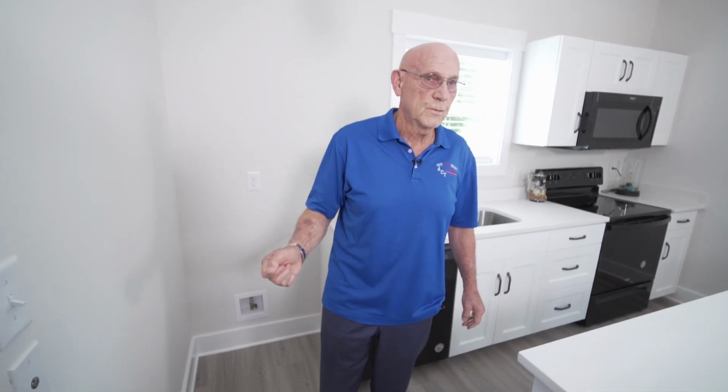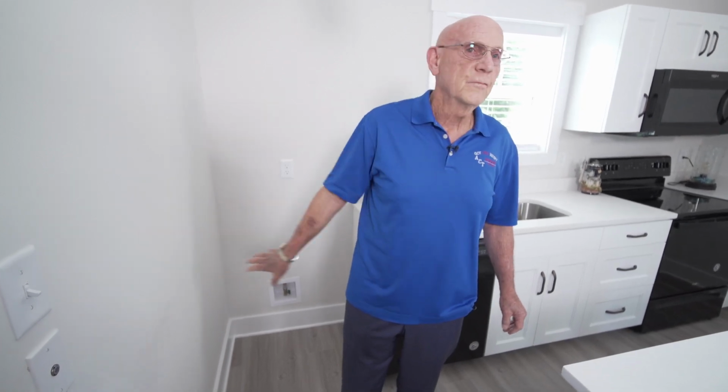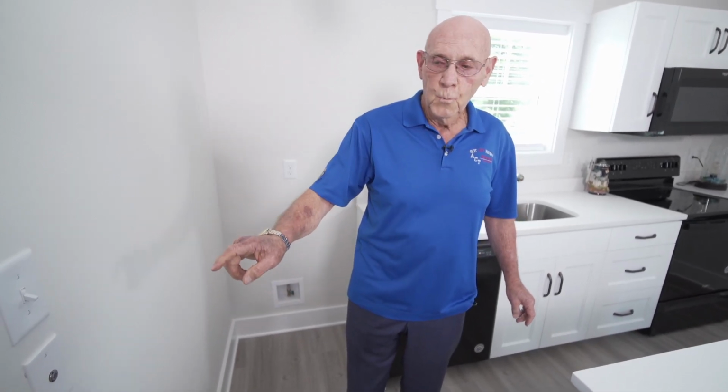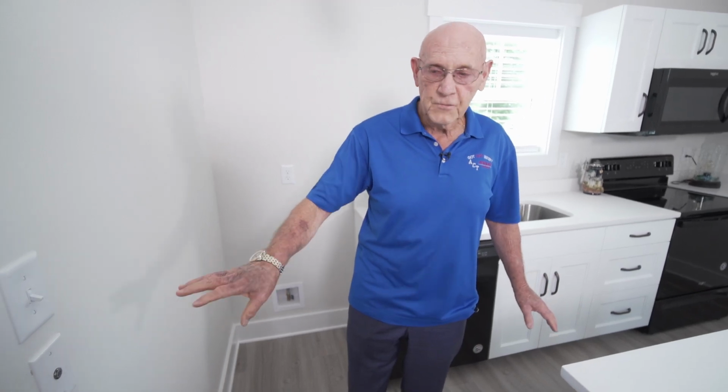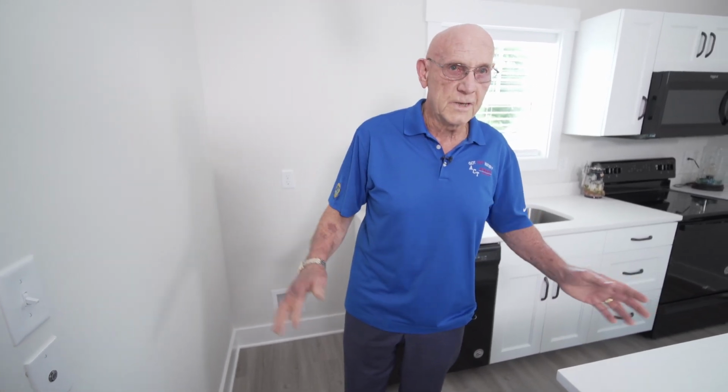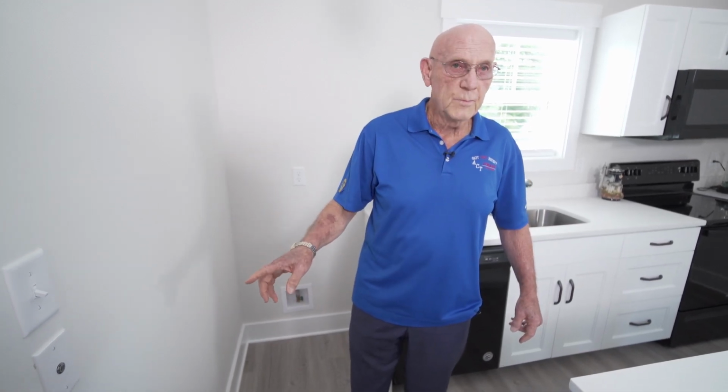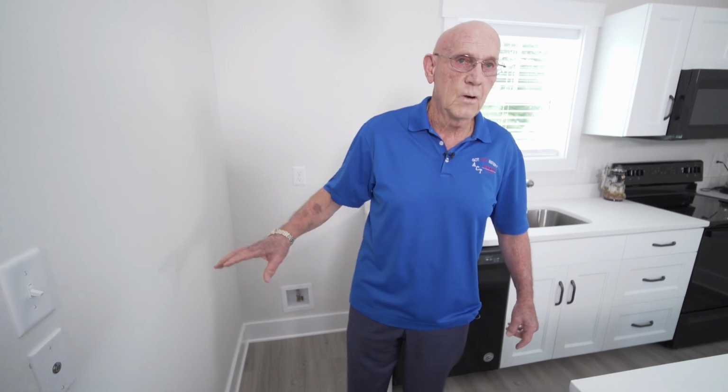So when you turn a fixture on, you're going to get it within 2 to 3 seconds without running water down the drain. Because that is a lighted button, it only operates when the pump actually runs. If hot water is already in the line, it'll do just exactly what you saw. It'll go on green and shut off immediately. When you haven't used hot water for a while, it'll stay green for approximately 30 to 40 seconds to distribute the hot water. Once the hot water is distributed, then all of the lights go off.